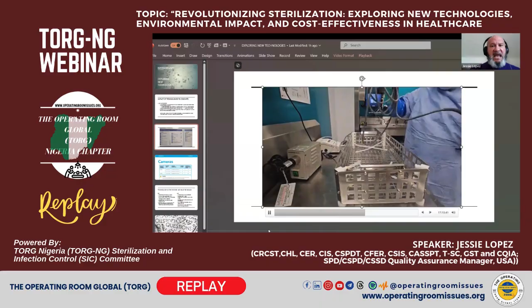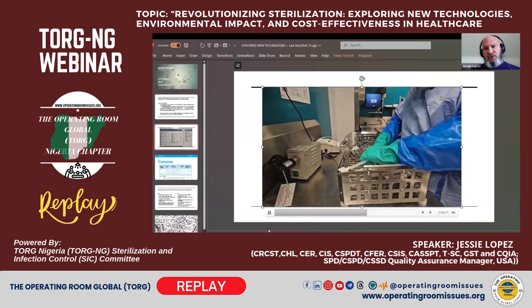It's going to use hoses to flush and irrigate the lumens of your device. And it's going to give you a thermal disinfection step here. The IFU just calls for ultrasonic cleaning. But as I showed you earlier, there are 3 steps after ultrasonic cleaning that if you utilize a basic ultrasonic cleaner, you're going to have to re-rinse your device. You're going to have to reflush your ports. And you're going to have to use thermal disinfection after the leak testing of this device.